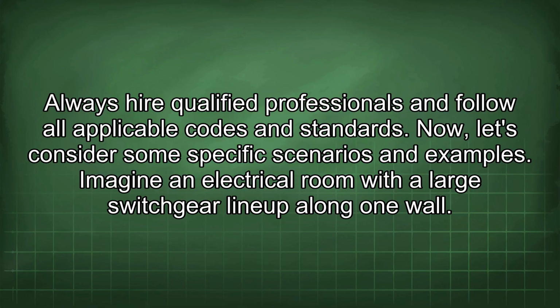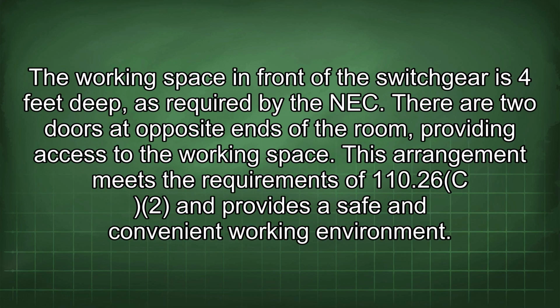Now, let's consider some specific scenarios and examples. Imagine an electrical room with a large switchgear lineup along one wall. The working space in front of the switchgear is 4 feet deep, as required by the NEC. There are 2 doors at opposite ends of the room, providing access to the working space. This arrangement meets the requirements of 110.26(C)(2) and provides a safe and convenient working environment.